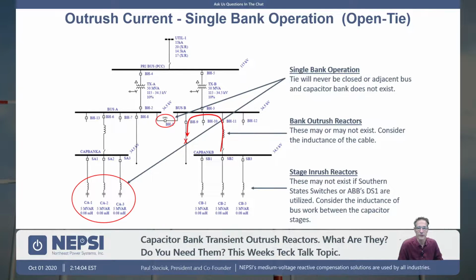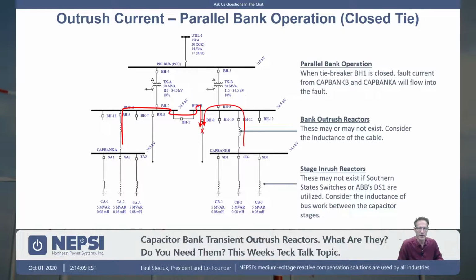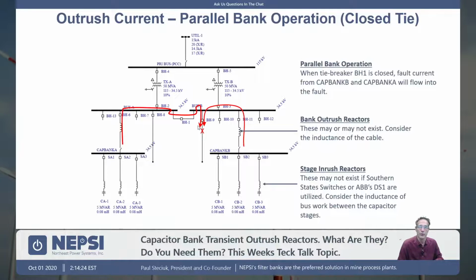result in current flow. So think about this: if you have a main tie main system, you want to design the system for the condition where the tie breaker is closed, because the situation there is we have basically, sometimes, doubled the amount of capacitance or the amount of discharge current into that fault condition at that location. So when doing the sizing calculations to determine the reactance required to do the analysis, make sure that if it's a main tie main, you consider the tie closed in your calculations, and that's really the true value of inductance that you will want.